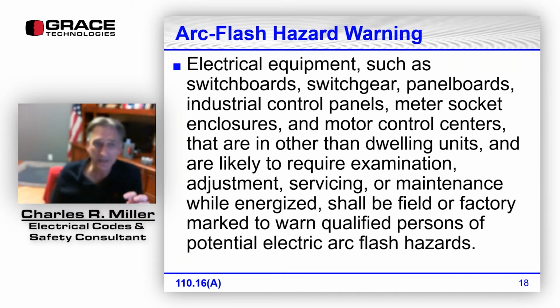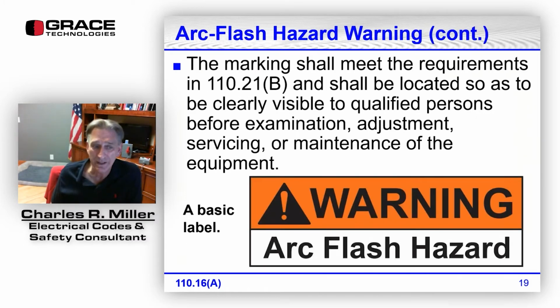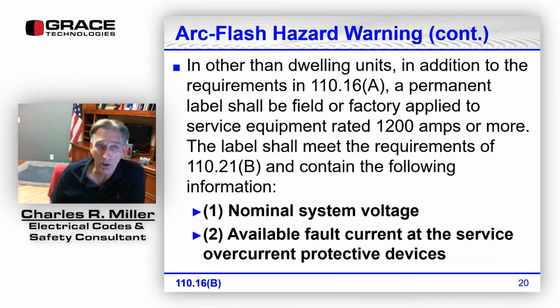All right, so here's an example of the general warning label, a basic label that's required by the National Electrical Code. This marking has to meet the requirements in 110.21(B) and has to be located so as to be clearly visible to qualified persons before examination, adjustment, servicing, or maintenance of the equipment. This is 110.16(A). This was a change one or two editions back where they added another section, because this is all that it used to be for a while. So this stipulation became 110.16(A).